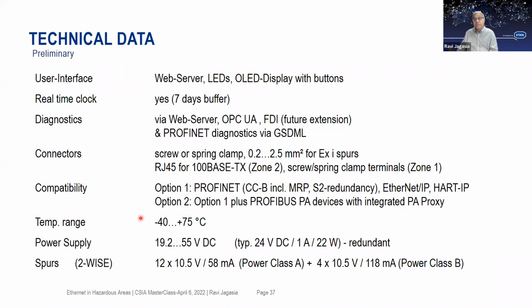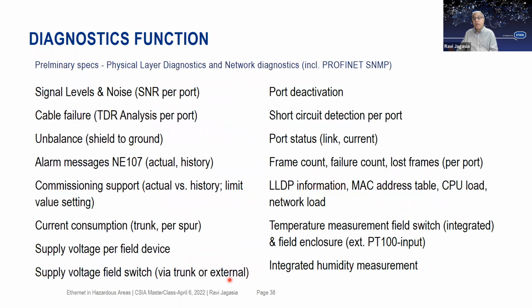Temperature ranges are good, -40 F to 165 F. Power supply requirements, spurs, what is the power that's coming out? Signal level, cable failure analysis. This could be a very important diagnostic feature. Unbalanced alarm messages as per NE 107. Current consumption, so you know if any field device is misbehaving and drawing more current, you could detect that and would be able to create an alarm.